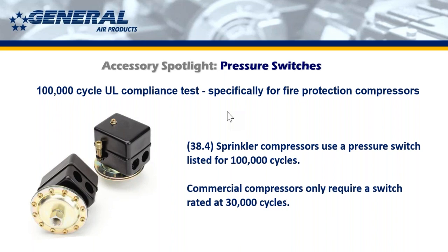So that's UL taking random pressure switches from us from time to time and running them to make sure that they go to 100,000 cycles. Once they run them to 100,000 cycles, we tell them run it to death. And at that point, the pressure switches that we use typically fail around 200 to 250,000 cycles. Again, trying to understand the difference between what goes into a fire protection air compressor and a retail air compressor. A retail air compressor's pressure switch is going to last about 30,000 cycles, as opposed to 100 to 200,000 cycles like the professional duty ones that we use.